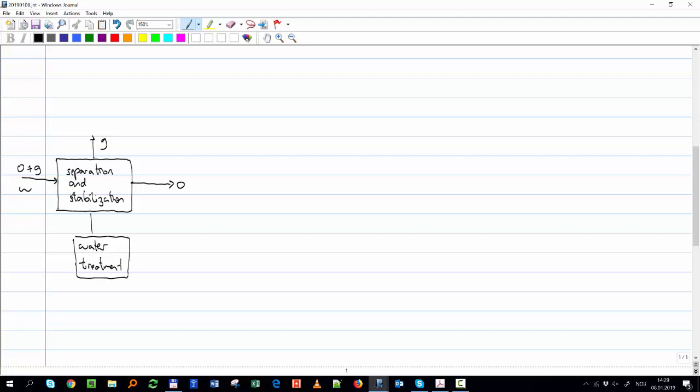So we said here, how much was it? 500 to 1,000 ppm. Be careful with the units of ppm. You have to know if it's weight or volume, what is it that you're dividing? And they have to be the same units. And when it comes out of here, I can have two, but mainly basically it is 100, oil in water, and here will be 40.